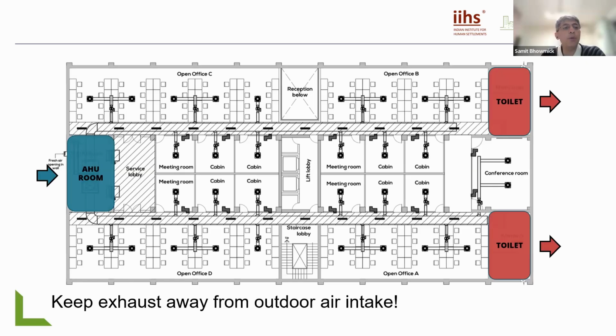It's going to be difficult to retrofit that into an existing building because it depends first on the scale of the building. That's something you need to keep in mind before you decide radiant or non-radiant, because in radiant cooling you'll require two sets of cooling temperatures, one which removes moisture and one which just removes the sensible heat from a space. In an existing building it's difficult to integrate another chill water system if the piping has already been done, so it's not easy to pull off. Even if you are able to do that, you need to look at the scale, because smaller buildings are very difficult to pull off. You don't need equipment that gives you higher temperature chill water in smaller buildings, smaller capacity. That's a concern you'll have to watch out for.